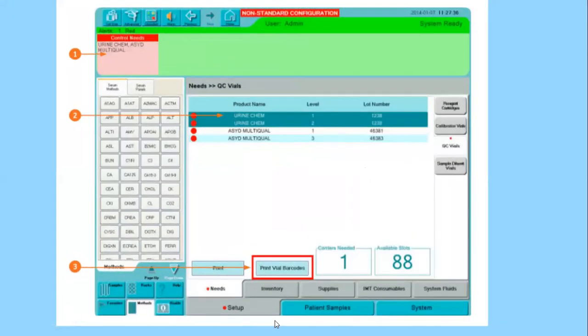Now, this is if we pull off any QC and the machine will automatically do inventory and see what it needs. So the control needs will pop up in a little red box. It'll say control needs up at the top. This one needs the urine chemistry controls and then multi-qual controls. So they will be shown here in the needs. And you can switch between these screens on the little right-hand column. There's those little buttons. So you have your reagent cartridges, calibration vials, QC vials, and sample dilutant vials.